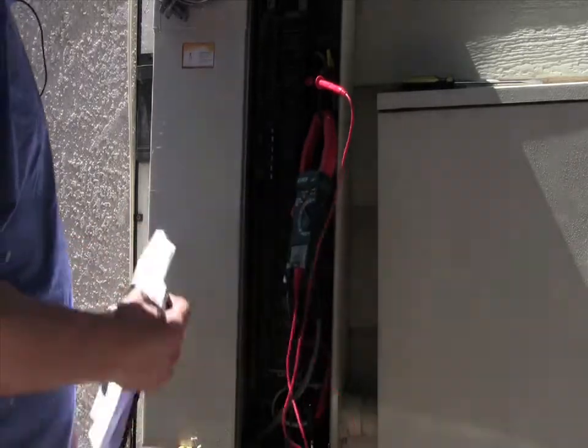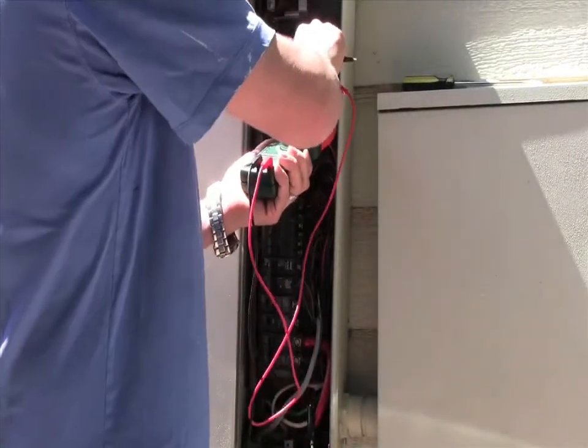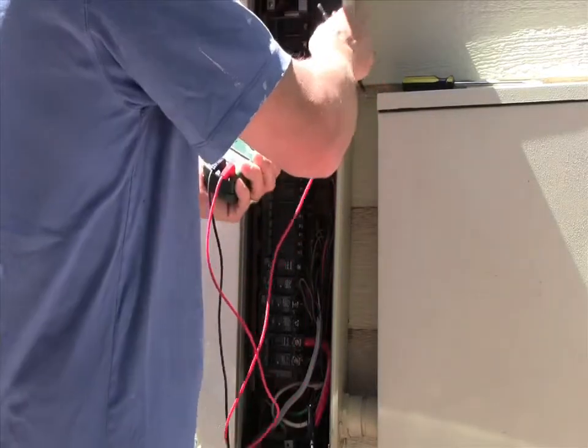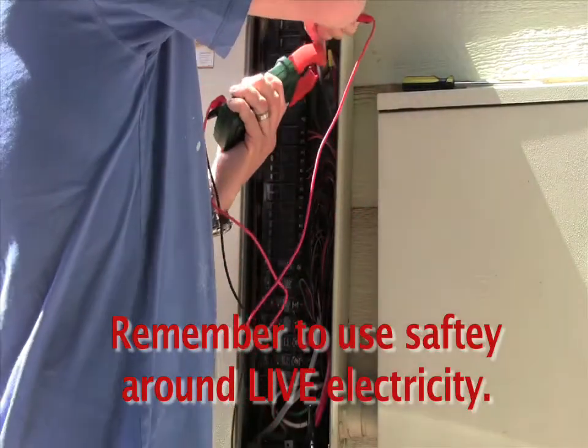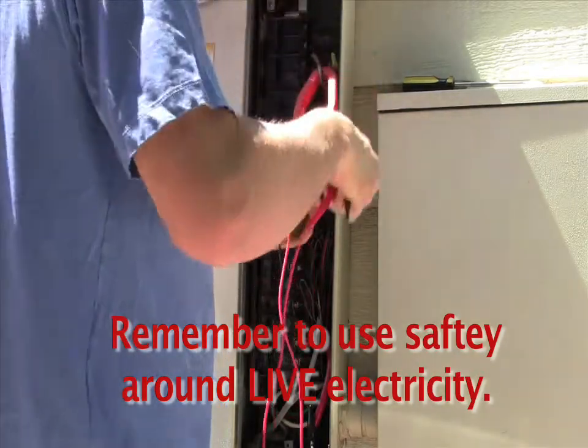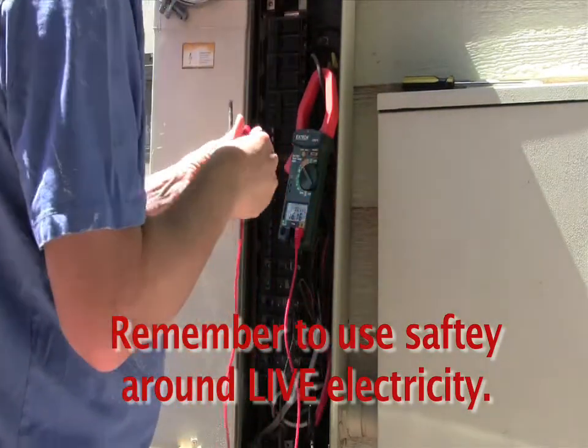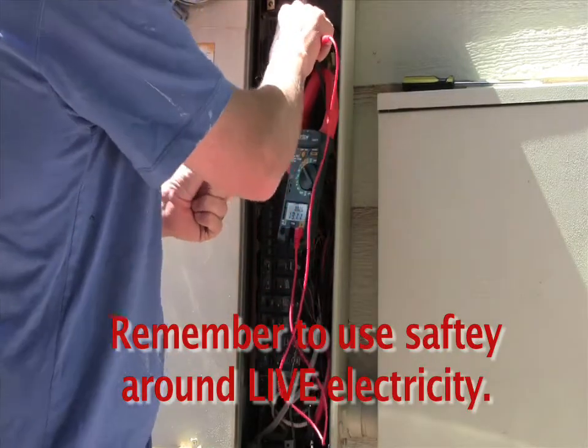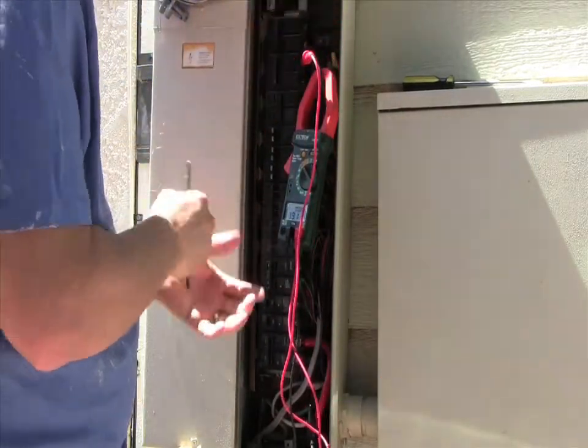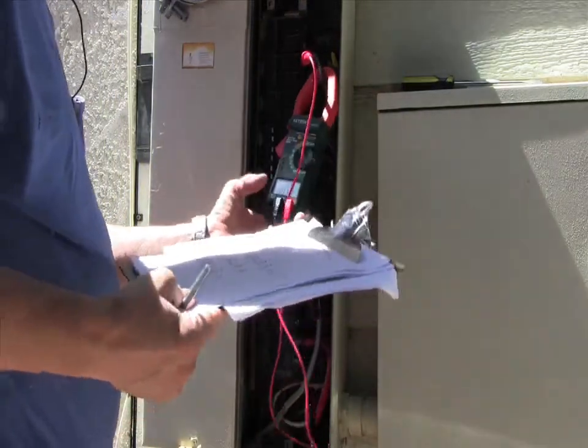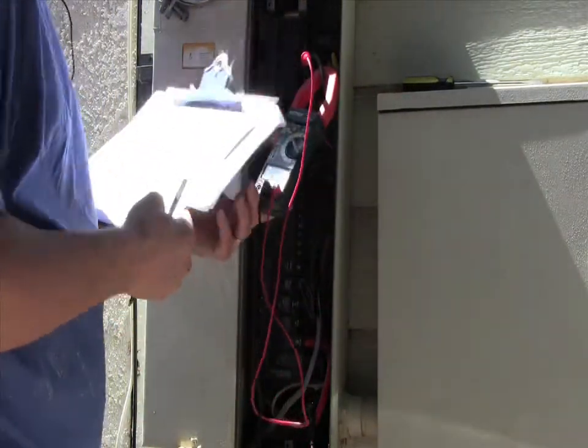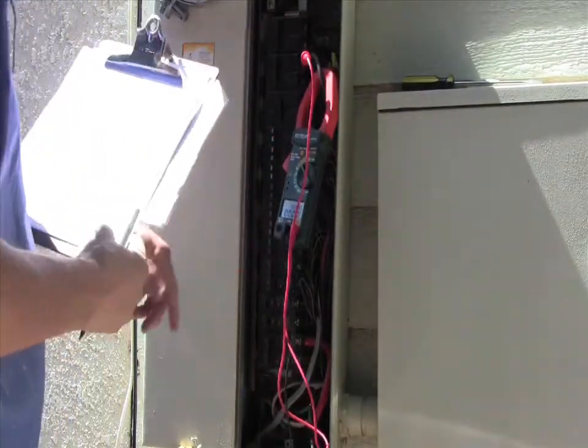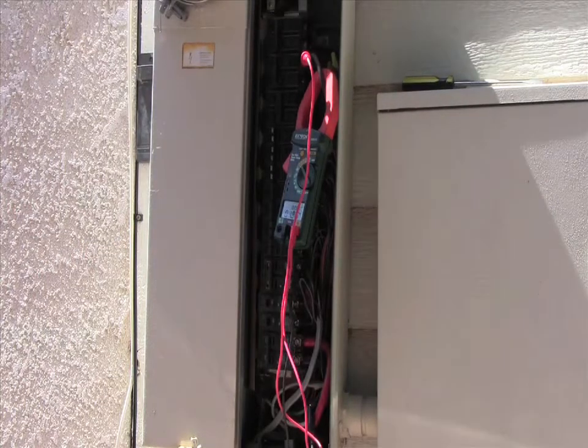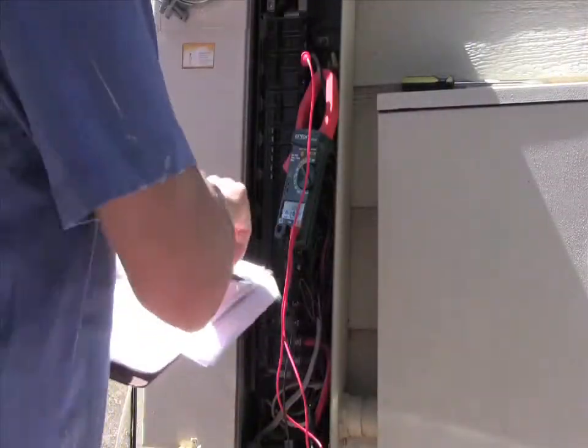So now we're going to clip on to lead number 2. Be very careful, because this box is energized. You don't want to get electrocuted, or even shocked very much. Now we're going to clip on to this lead right here. We're going to let it calibrate for about 30 seconds. Okay, it's been a little over 30 seconds, but that's alright. So we'll go through and check our readings.